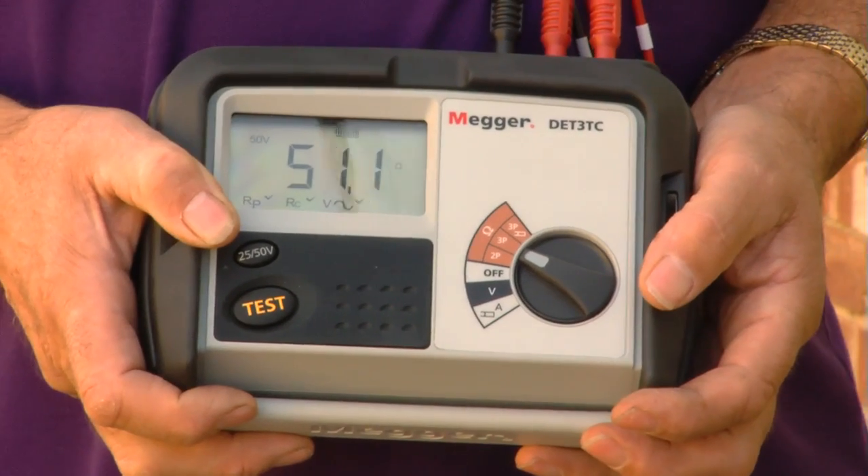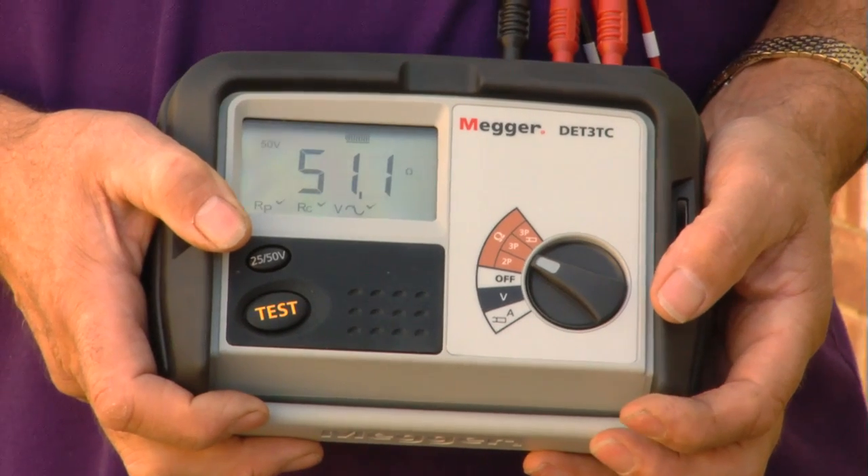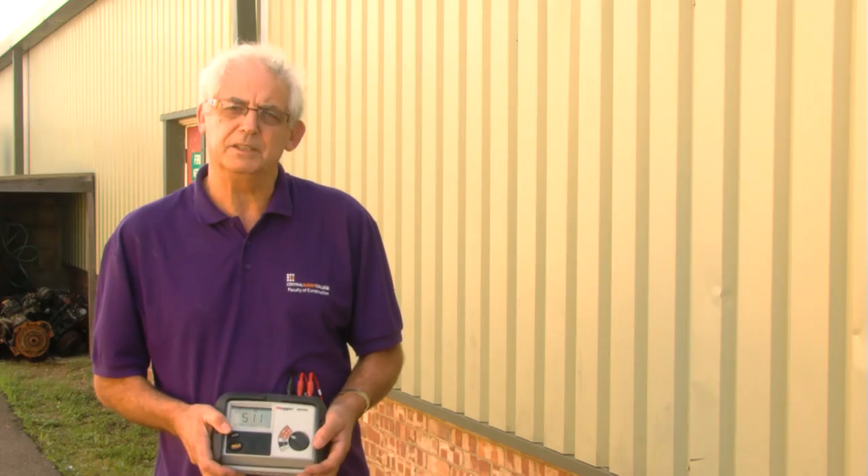We can see now that we've got a resistance value of 51.1. It's dramatically reduced the resistance value, so two earth electrodes would be better than one in this instance. To get a very accurate reading, I would need to repeat the three tests by moving the potential electrode ten percent this way, ten percent the other way, and taking an average of the three readings. That would give me the reading I would write down on my test certificate.